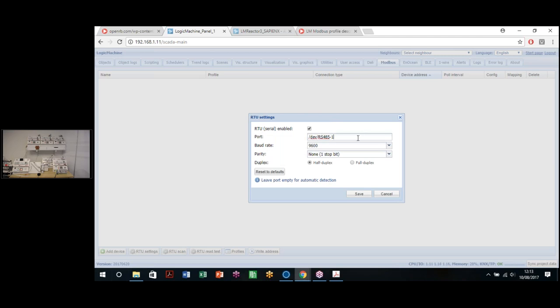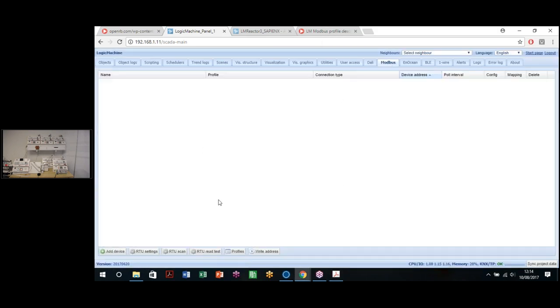Here we write the port. This port name, we can find it in the system configuration, in the status tab. We can see all the available serial ports that we have. In this case, we configure the baud rate and all the information that we have taken from the manual of the device. Once we save, the Modbus is already, let's say, enabled.